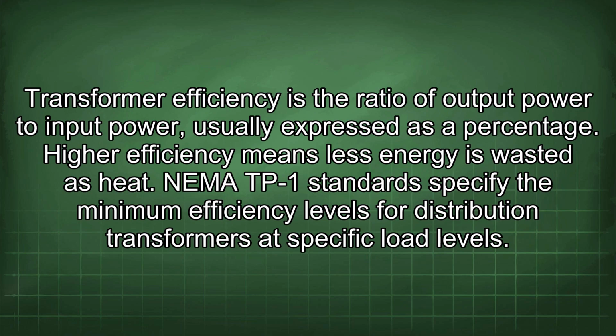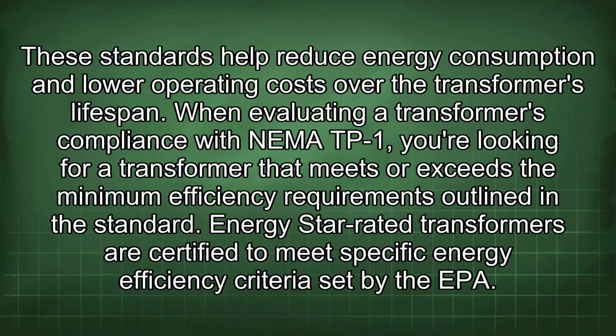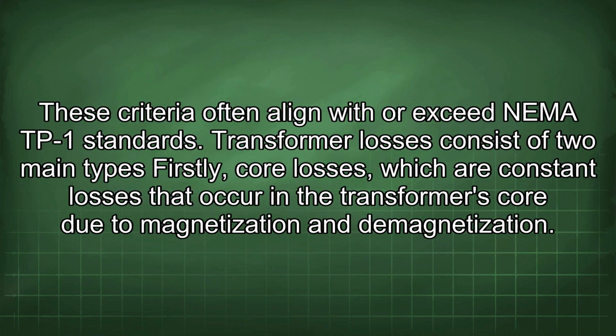Transformer efficiency is the ratio of output power to input power, usually expressed as a percentage. Higher efficiency means less energy is wasted as heat. NEMA TP-1 standards specify the minimum efficiency levels for distribution transformers at specific load levels. These standards help reduce energy consumption and lower operating costs over the transformer's lifespan. When evaluating a transformer's compliance with NEMA TP-1, you're looking for a transformer that meets or exceeds the minimum efficiency requirements outlined in the standard. Energy Star rated transformers are certified to meet specific energy efficiency criteria set by the EPA. These criteria often align with or exceed NEMA TP-1 standards.